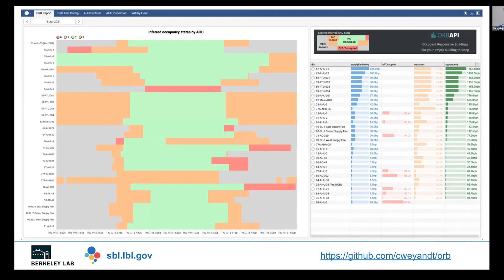To provide a final scale, looking at the opportunity of these units, it varies dramatically by the size of the system. So we took the one data point we have consistently for every air handler - the size of the supply fan - and multiplied that by the number of hours it was in that state. We end up with a metric of horsepower hours, which is a little silly metric, but it gives us some idea of scale for where we should focus our attention and trim these schedules back.